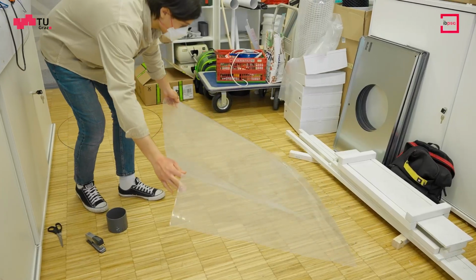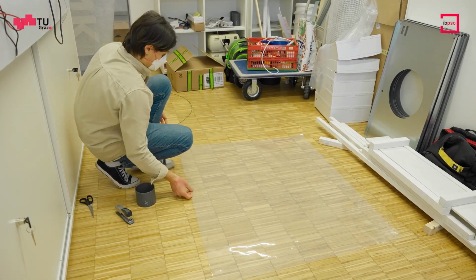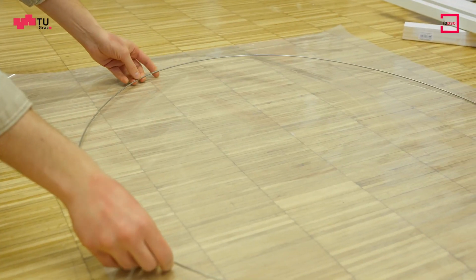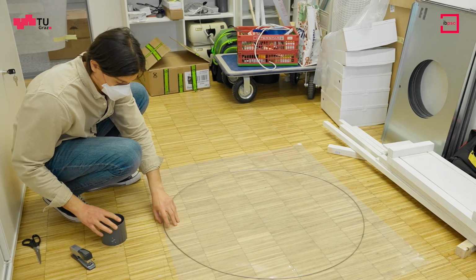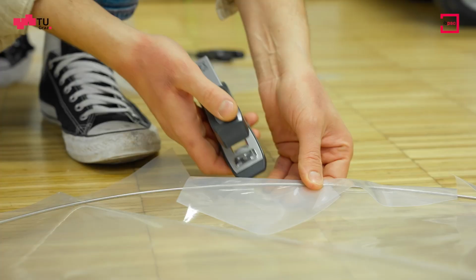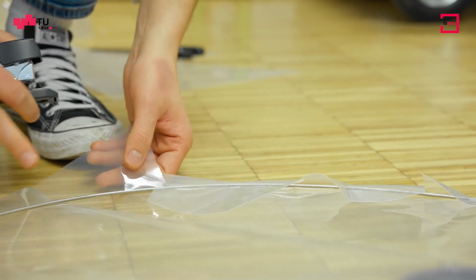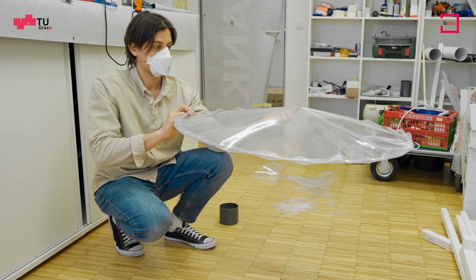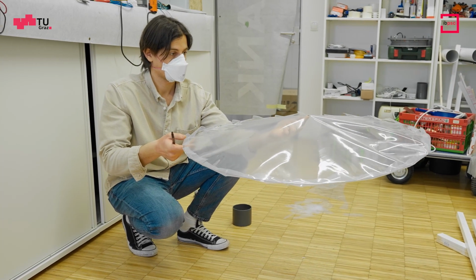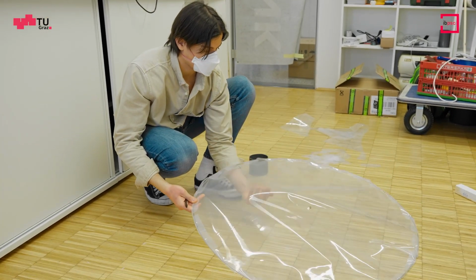The hoods are pre-assembled using thin polythene sheeting or cellophane, which is wrapped around a circular wire frame and either stapled or taped into place at the edges. It's important that the hoods are not too taut, as they should form into a shallow cone shape when they are suspended in a level position. The cone shape is designed so that the hoods catch the aerosols as they rise up on the warm air plume rising off the person seated below.